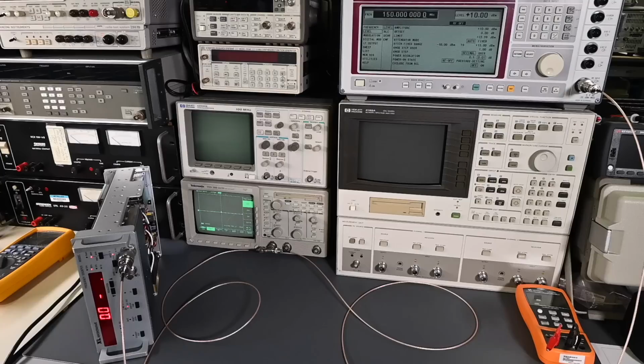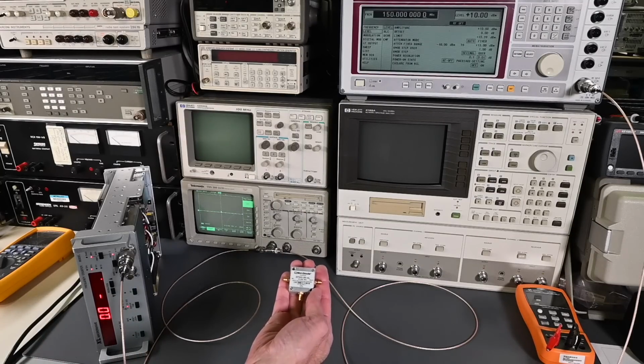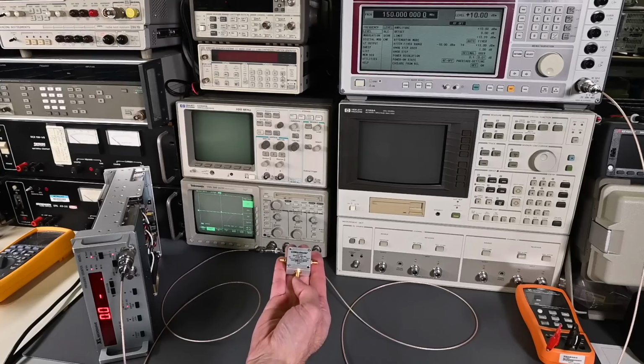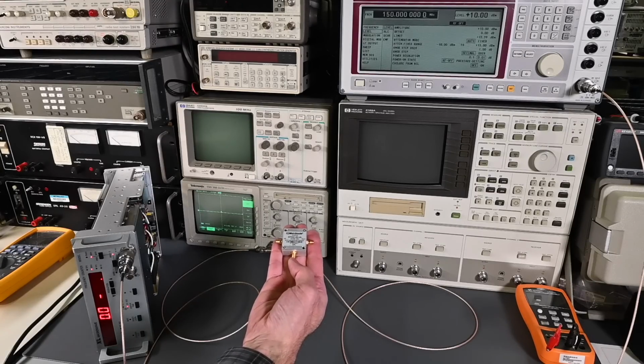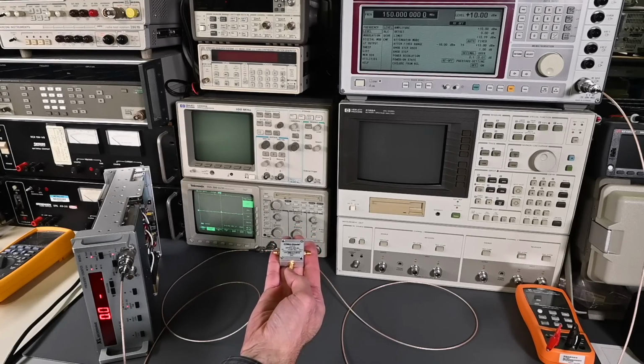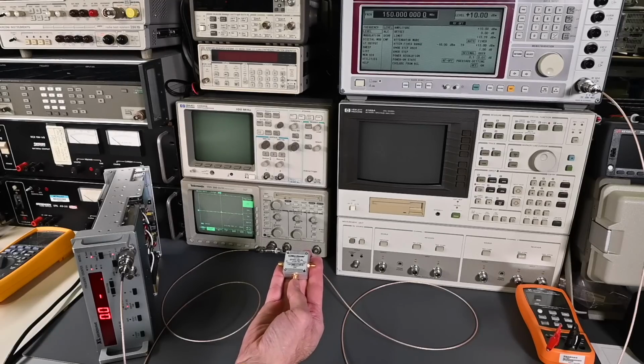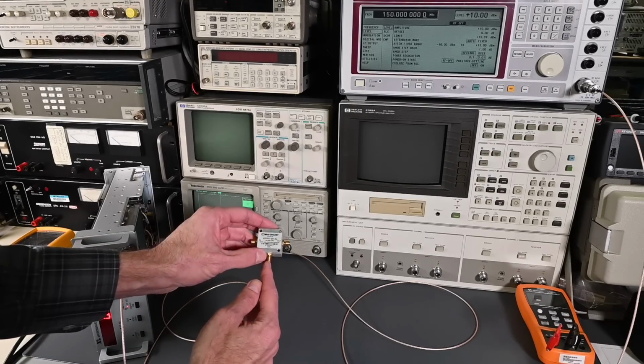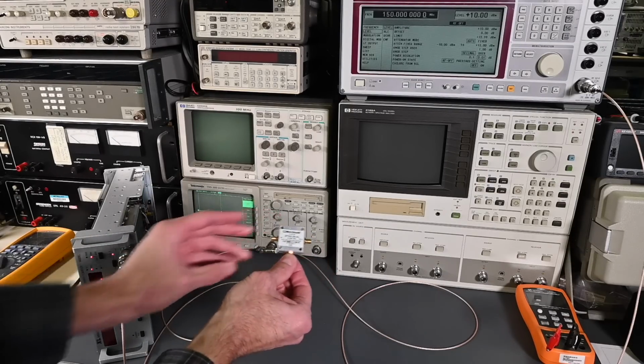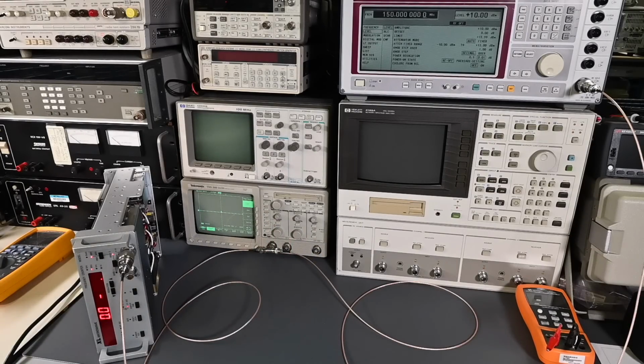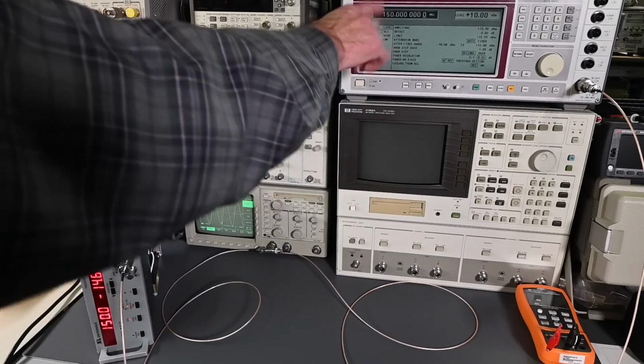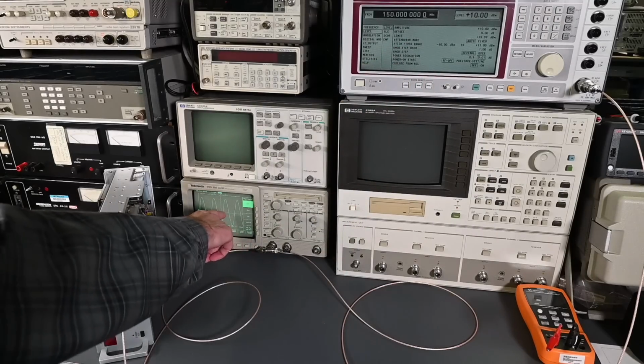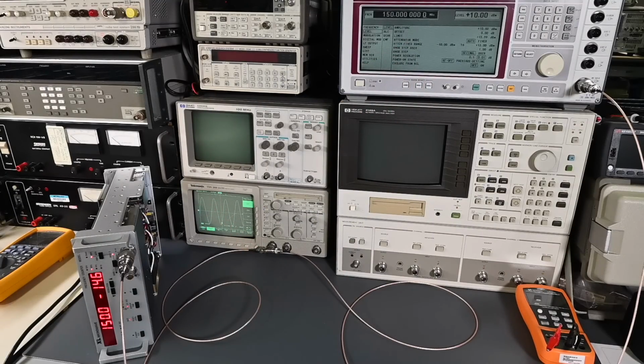A coupler like this right here has a 50 ohm impedance on the input and then the output, and then the coupled side right here on the center connector at the bottom, that would go off to the oscilloscope or the instrument you're taking the measurement with, and it basically isolates this output from the input and the output. So normally this is what you'd want to use if you were trying to measure the signal and send it over to an oscilloscope. All right, so going back to this setup, if I go over here and I turn this back on, okay, so we have 150 megahertz plus 10 dBm output. You can see the displayed signal on the oscilloscope, okay, and the actual value and so forth isn't really important at this point.